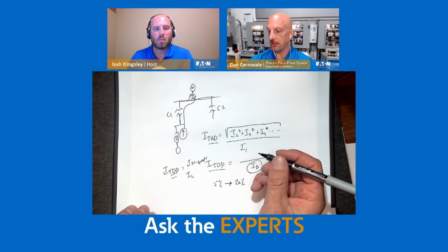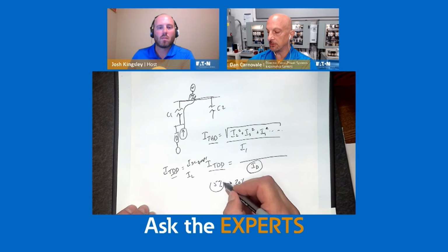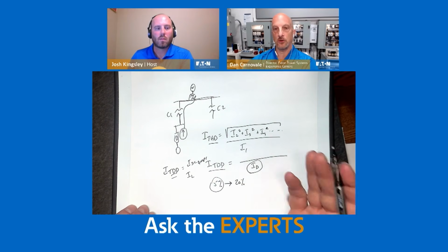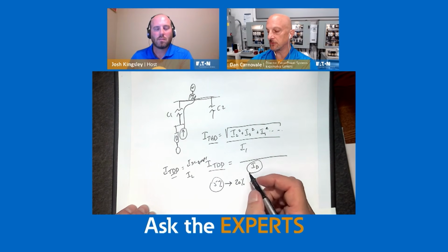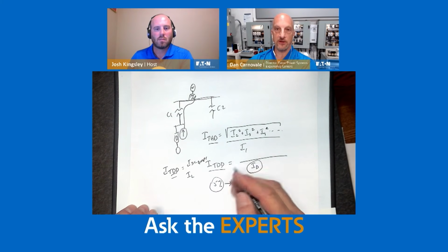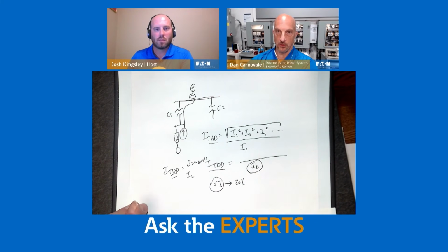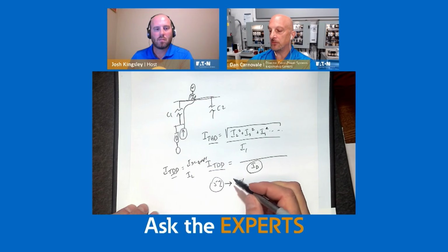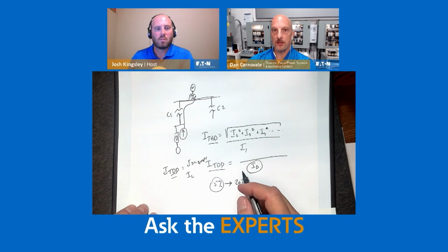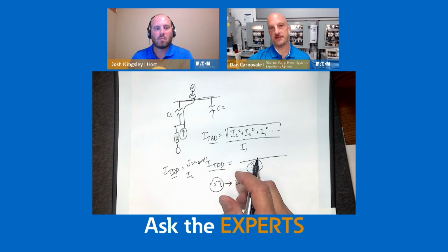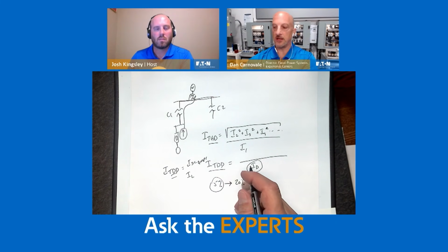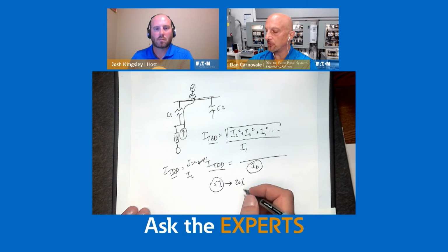Now, if you look at an 18 pulse drive, most of the time you're going to be below that 5%. So that's where, going back, Josh, to the original question that we talked about, you don't even have to deal with it at that point because it already, quote unquote, complies. But when people say comply, that's a little bit of an interesting thing, because the way the standard is written, you only comply at the point of common coupling. So people sometimes use it down into the system, and we could talk about that more if you want.